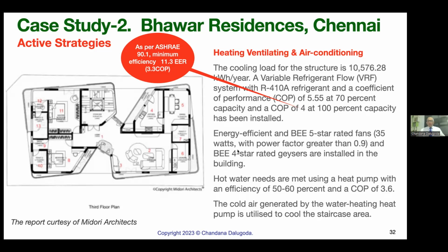Hot water needs are met using a heat pump with an efficiency of 50 to 60% and COP of 3.6. The cold air generated by the water heating heat pump is utilized to cool the staircase area. Now that is being done even in Sri Lanka. Now, heating by electricity is a crime. We can't use it. If we use a heat pump, what is a heat pump? A heat pump is a refrigeration machine, but it uses a main energy source to heat. It is the reverse cycle of a refrigeration machine.